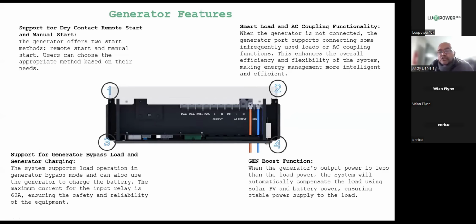It's called an GEN Boost function. Now, previously, when we ran a generator, our relay from the DC side on the PV was disabled to supply load, purely because we didn't want any leak current going to the generator, for obvious reasons, damaging the generator. But now we have what's called an GEN Boost function, and you can enable it. As an installer, you have the power to enable it.